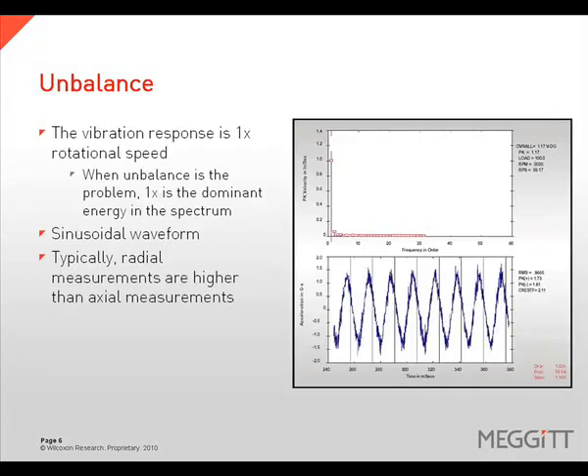When imbalance is the problem, the vibration response will occur at 1 times rotational speed, and the 1 times is the dominant energy in the spectrum. The waveform will be sinusoidal, and typically the radial measurements are higher than the axial measurements.